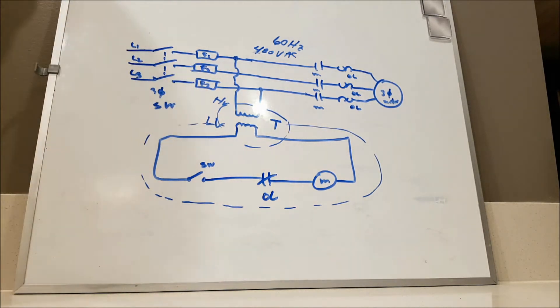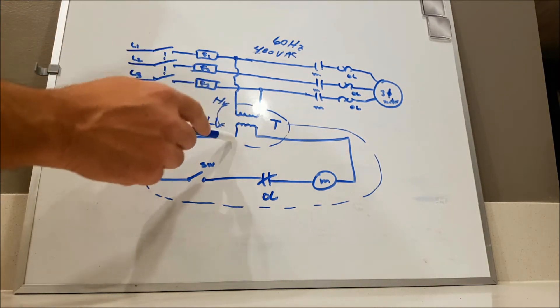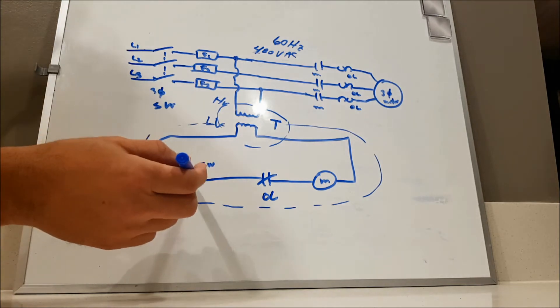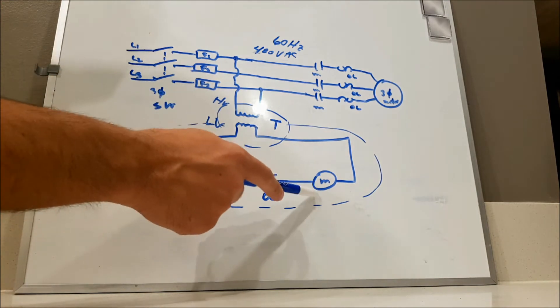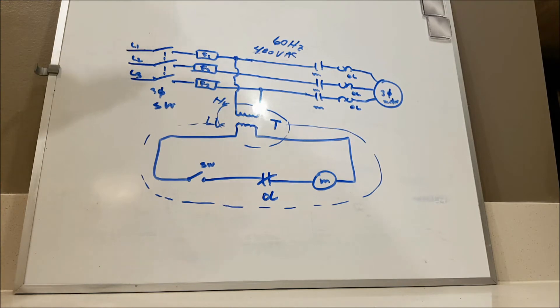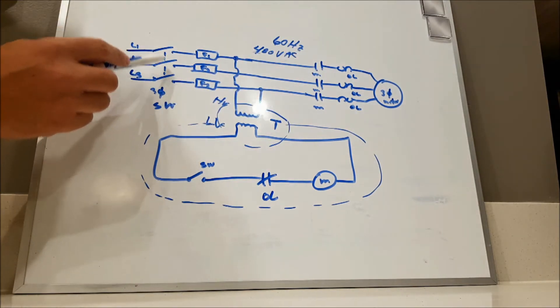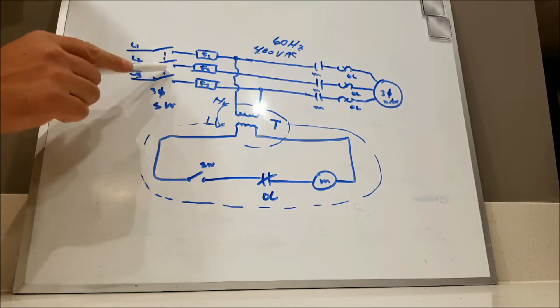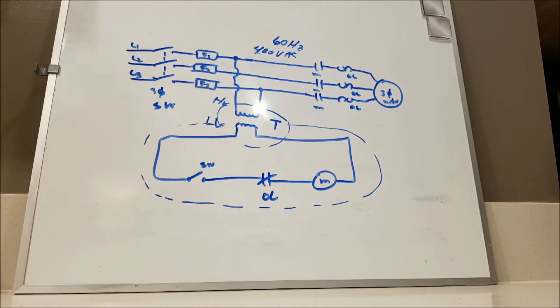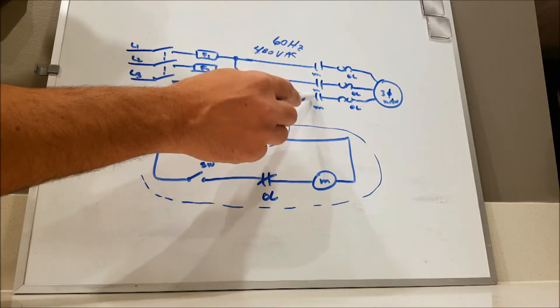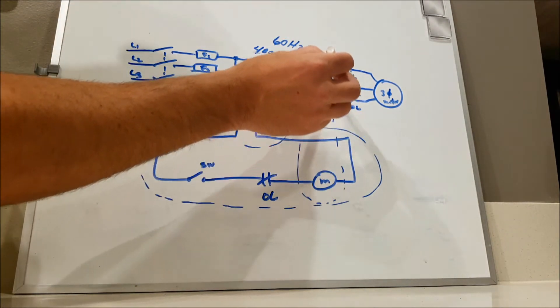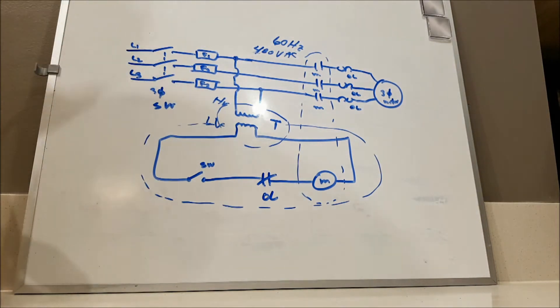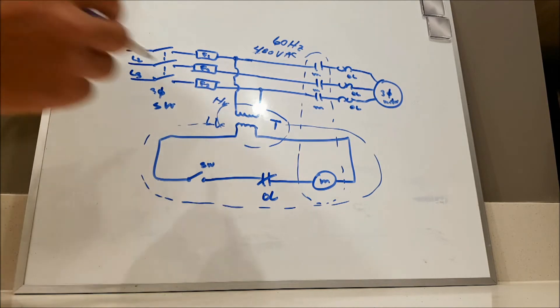I'll now go over each component of this system. We will need a transformer to step down the voltage. Within the control circuit we need a normally-closed contact from the overload and the coil. In the power lines we need a three-phase switch that opens and closes all three lines at the same time, a fuse in each line for overcurrent protection, and three normally-open contacts — one per line — which belong to the three-phase contactor or motor starter.